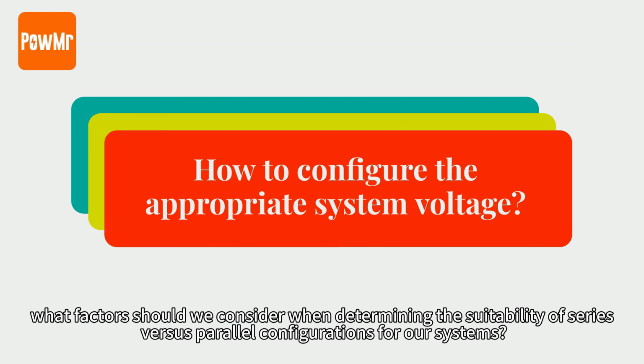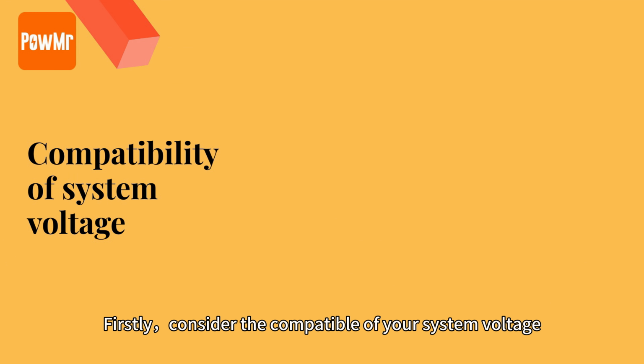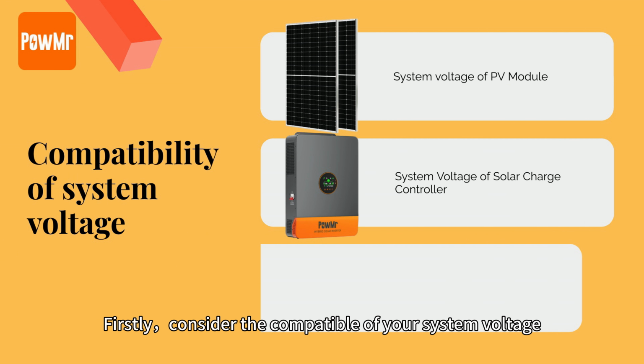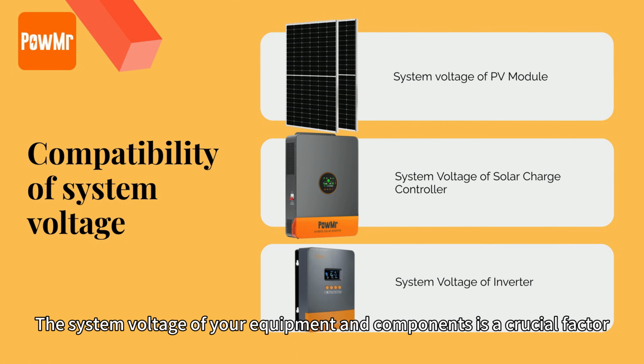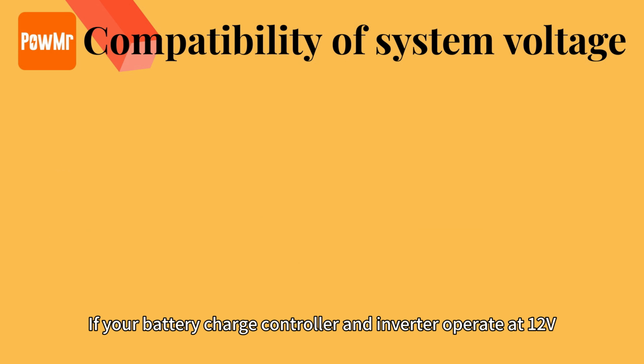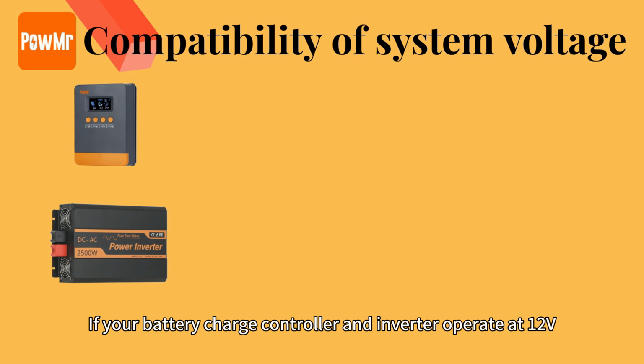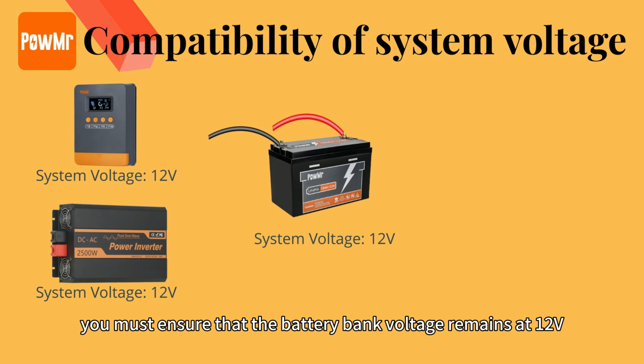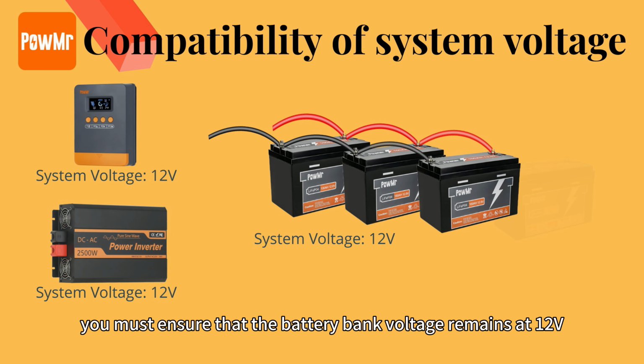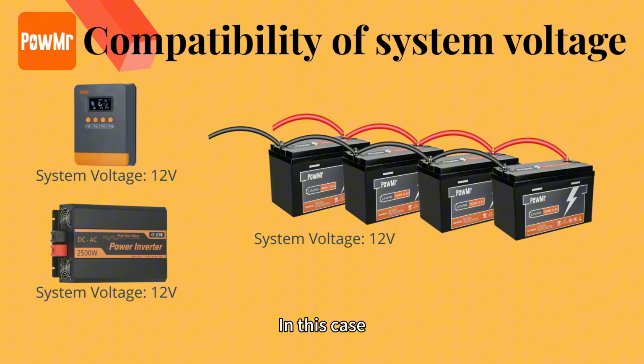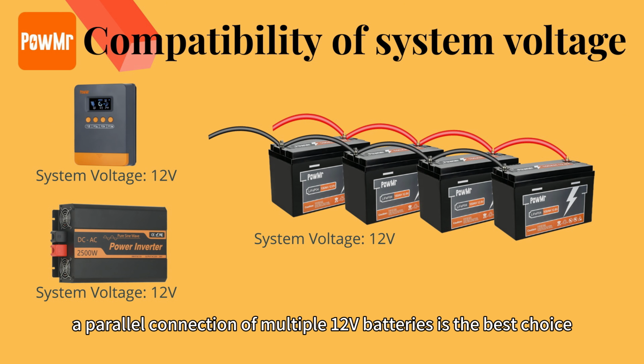So what factors should we consider when determining the suitability of series versus parallel configurations for our systems? Firstly, consider the compatibility of your system voltage. The system voltage of your equipment and components is a crucial factor. If your battery charge controller and inverter operate at 12 volt, you must ensure that the battery bank voltage remains at 12 volt. In this case, the parallel connection of multiple 12 volt batteries is the best choice.